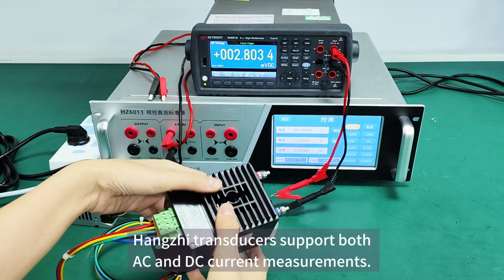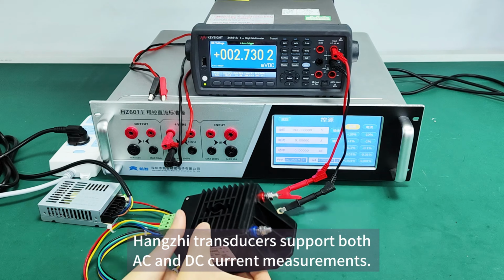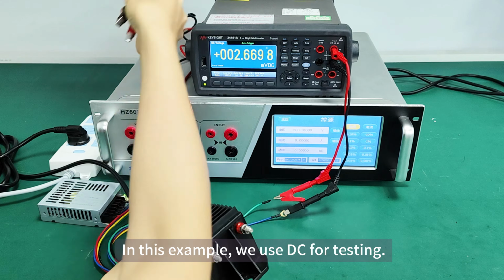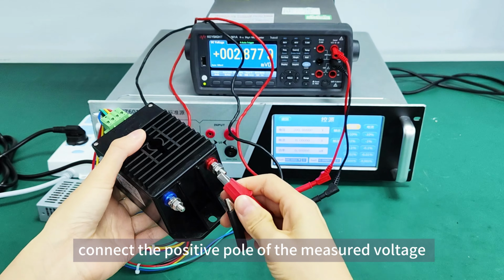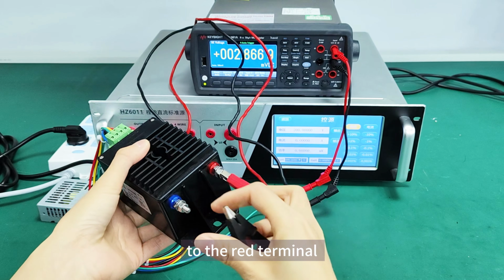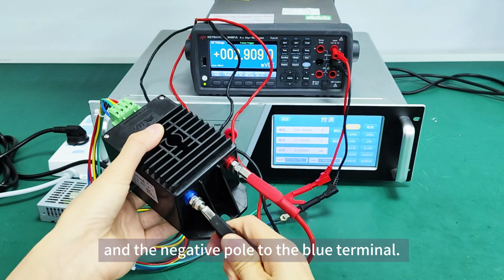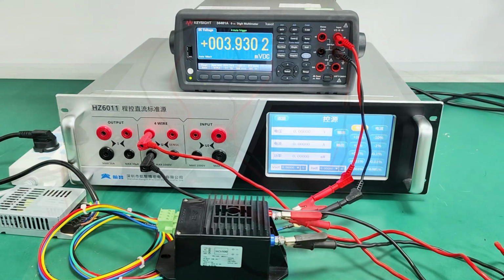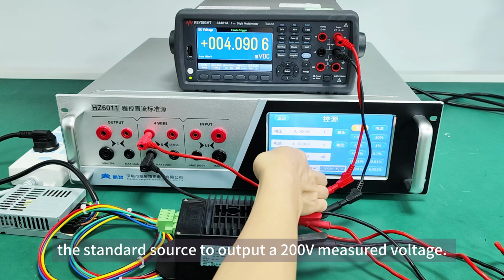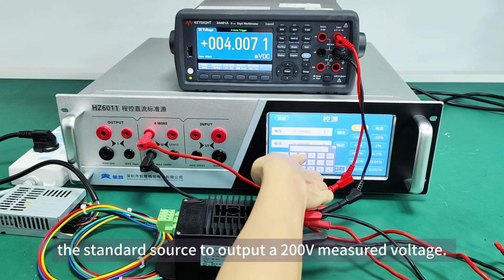Hangzhi transducers support both AC and DC measurements. In this example, we use DC for testing. During testing, connect the positive pole of the measured voltage to the red terminal and the negative pole to the blue terminal. Now we use the standard source to output a 200 volts measured voltage.